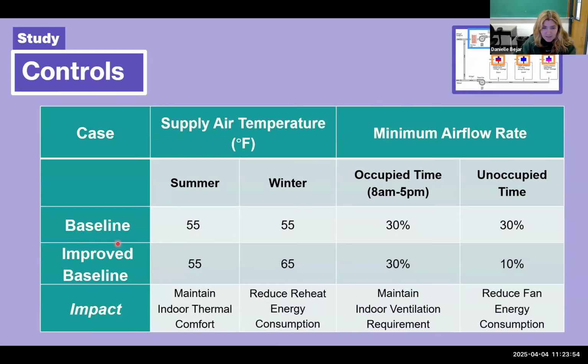Our baseline case here is first for the supply air temperature, keeping the supply air temperature at 55 degrees Fahrenheit. That's to maintain the room at 75 degrees, 50% relative humidity. So baseline has 55 degrees Fahrenheit fixed and then a minimum flow rate of 30% fixed during occupied and unoccupied time. That 30%, like I said, is to maintain indoor ventilation requirement, making sure there's adequate ventilation in the space.